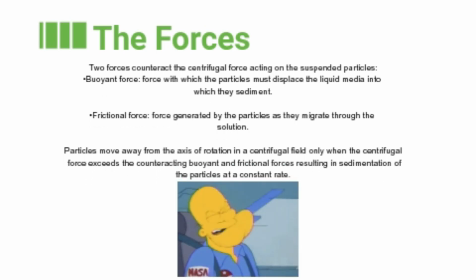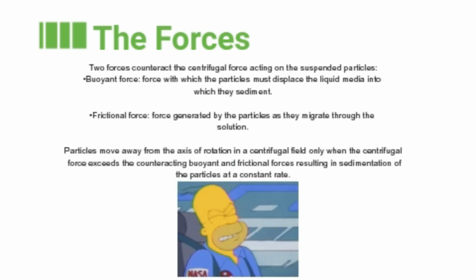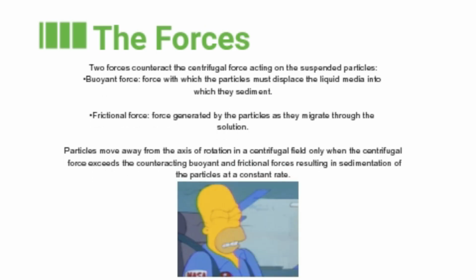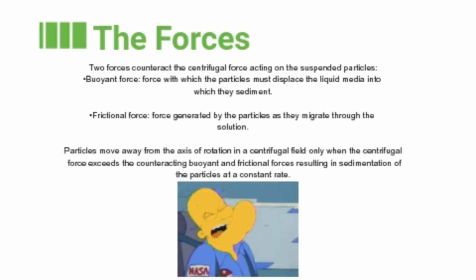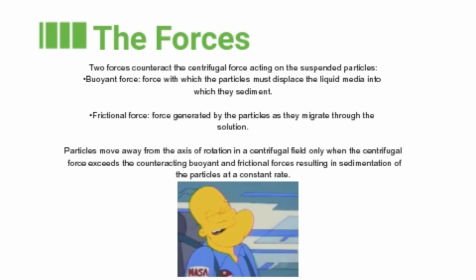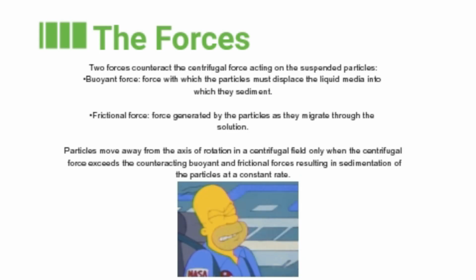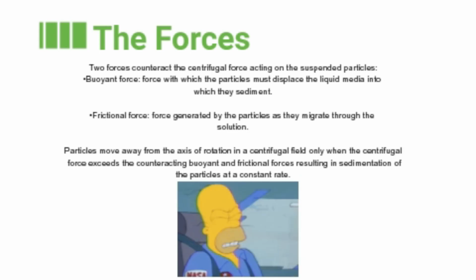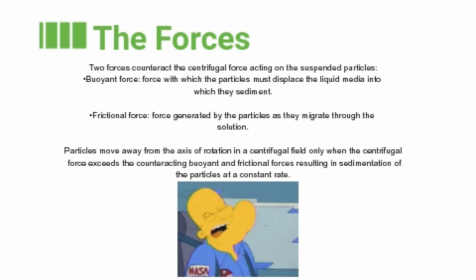Two forces counteract the centrifugal force acting on suspended particles: buoyant force, the force with which particles must displace the liquid media into which they sediment, and frictional force, which is generated by the particles as they migrate through the solution. Particles move away from the axis of rotation in a centrifugal field only when the centrifugal force exceeds the counteracting buoyant and frictional force, resulting in sedimentation of the particles at a constant rate.